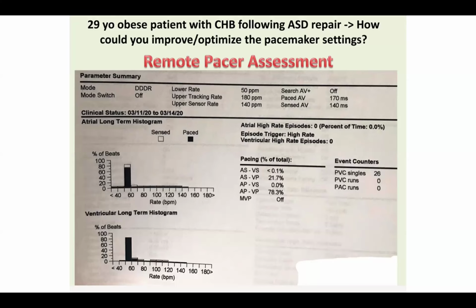So if you were going to assess this remotely, is there any way you could do that? I'm not sure about remotely, but I know in person you can bring them into clinic, interrogate the device, do threshold testing and adjust the sensitivity. Yes, so you could tell how good the device is at sensing in the office, right? We could lower the lower rate below the intrinsic atrial rate and see how it's sensing. So that's absolutely possible. So you're theorizing that maybe the reason the patient is pacing 78% of the time is because the atrial rate is really 70 most of the time, but the device is undersensing it and pacing even though the patient doesn't need pacing. Am I understanding you right? Correct, yes. So that's possible. I like that as a differential diagnosis of this issue. So that would be a reason.